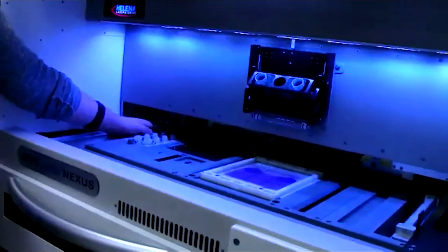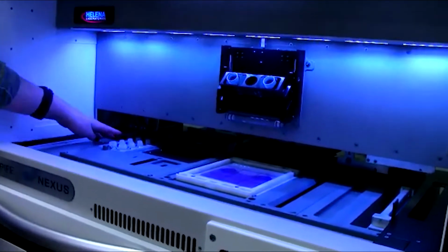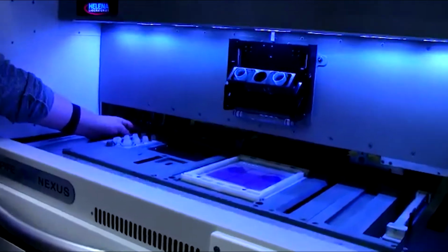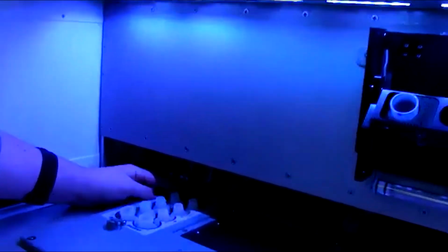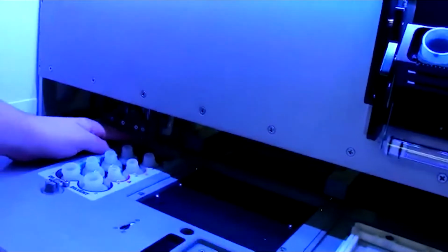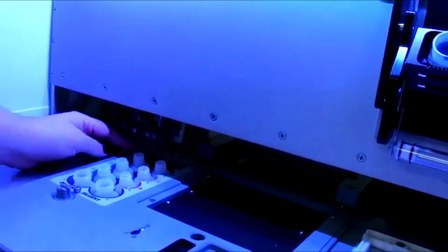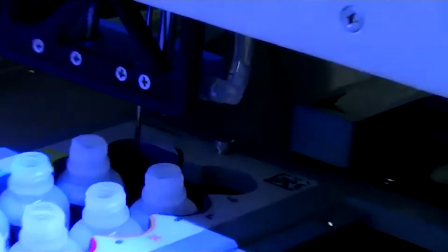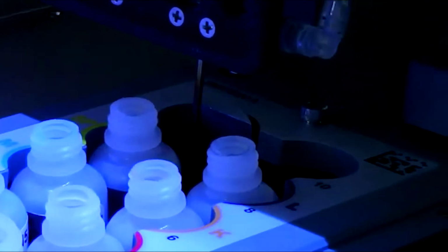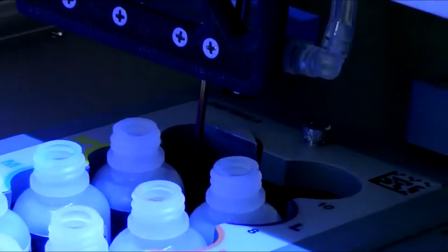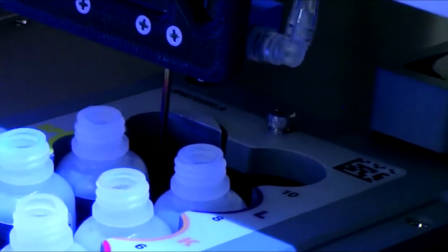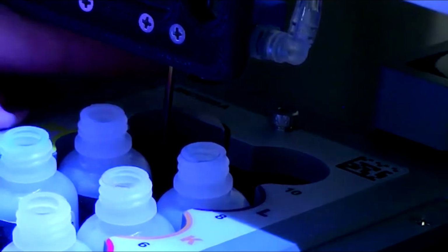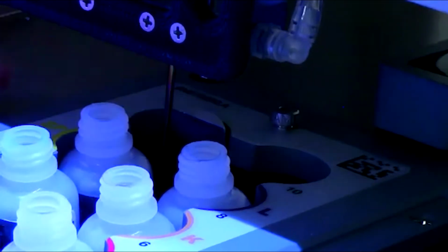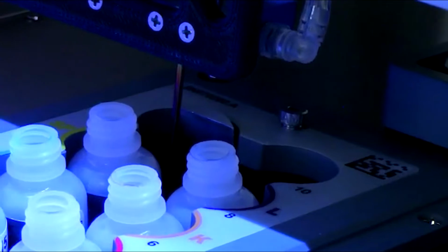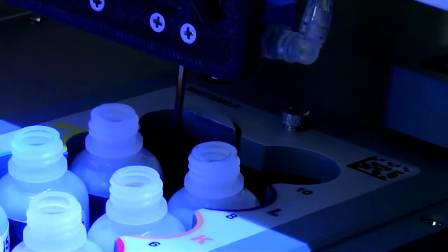And now you can see that the pipette is pressing down onto that jig to where it can no longer move freely. To change that calibrated position, I could just use our jog buttons over on the menu. If I jog it up a little bit, I just tap it once and I'll tap it again. Now it can move freely, and I can jog it back down if I want to change those calibrations again.